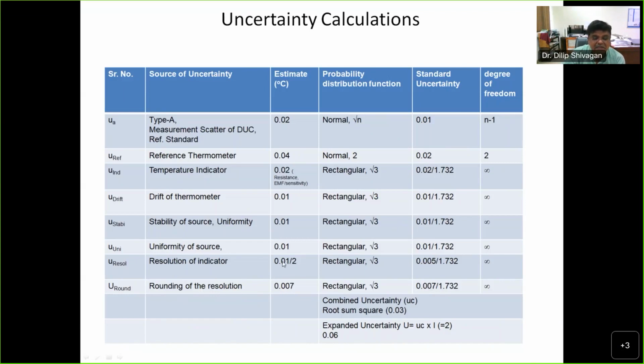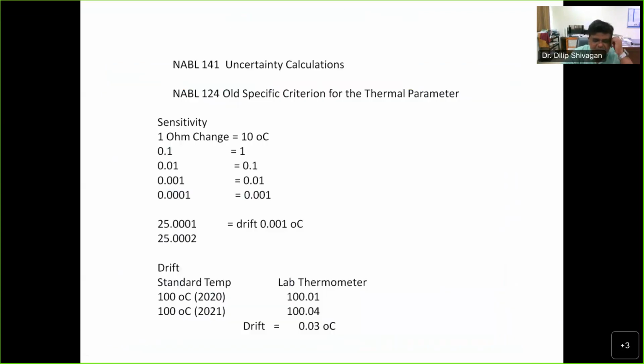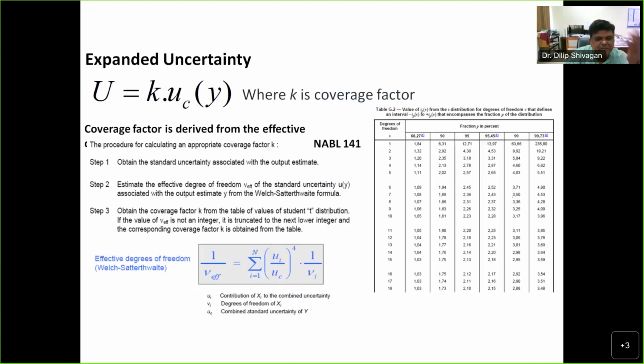In the case of this glass thermometer, sometimes we take the resolution even finer, because we can measure with very good traveling microscopes and other things. So as I said, for the coverage factor you have to calculate by this method. Up to 10, you are at about 2. So any parameter up to 2 also has very good confidence.